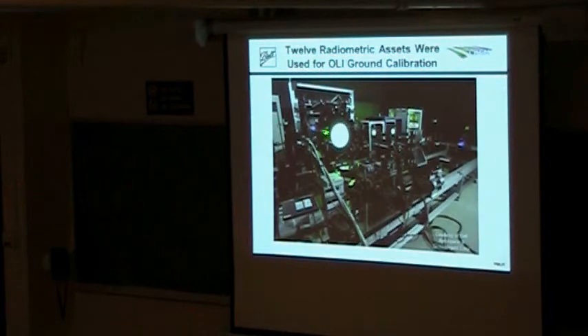All right, what you're seeing here is this Death Star sphere. Now you can see why we call it the Death Star. And it actually has a water-cooled jacket on it. Since you have, I think, about 300 watts of lamps here, you have to cool this thing. And interestingly enough, when you look at this data, it was so sensitive that the instrument could actually see those cooling lines in the data. It gave us structure. It wasn't very much, but there was enough structure in there that we actually had to characterize the sphere and then correct for that structure in order to show that we met requirements.